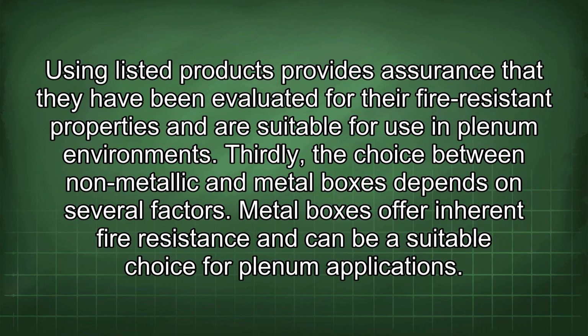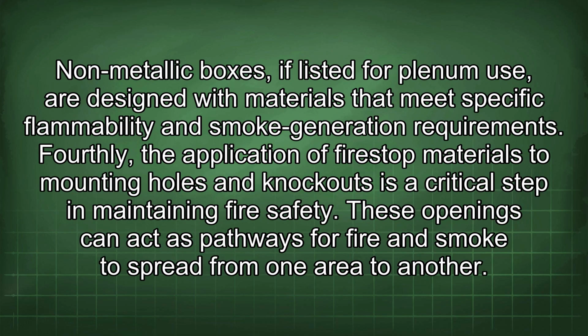Using listed products provides assurance that they have been evaluated for their fire-resistant properties and are suitable for use in plenum environments. Thirdly, the choice between non-metallic and metal boxes depends on several factors. Metal boxes offer inherent fire resistance and can be a suitable choice for plenum applications. Non-metallic boxes, if listed for plenum use, are designed with materials that meet specific flammability and smoke generation requirements.